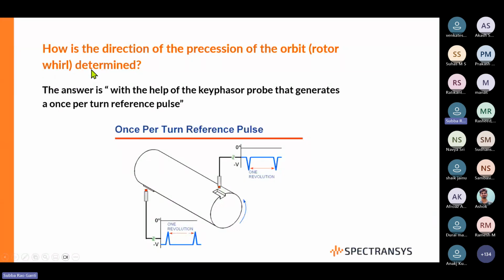So how do you identify it, and how do you get the direction? That information comes from your key phasor information. When the normal orbit happens without any key phasor dot, it looks elliptical, so you cannot say in which direction the orbit is moving, either the same direction as the shaft rotation or opposite. But once key phasor information is available, you can use that to identify whether the rotor precession is forward or reversed, or from X to Y or Y to X, whatever the case is.